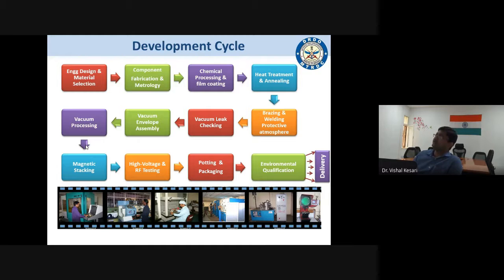Then heat treatment and annealing. The materials used are of UHV grade, ultra high vacuum grade. However, these metals keep absorbing atmosphere or other unwanted gases. So heat treatment and annealing are required to pull those gases out, because otherwise, since this is a vacuum device, when the electron beam flows inside, the trapped gases come out, make the vacuum poor, and the electron movement is disturbed.